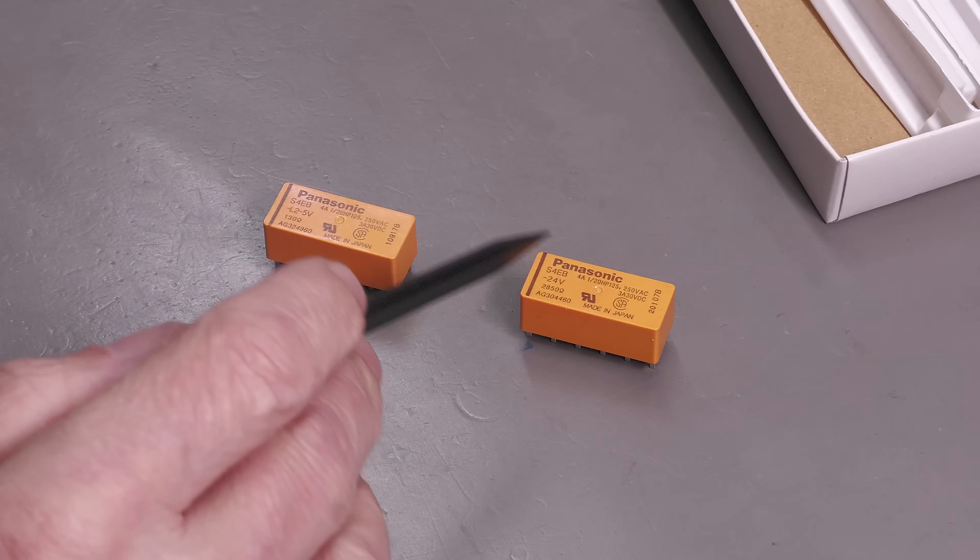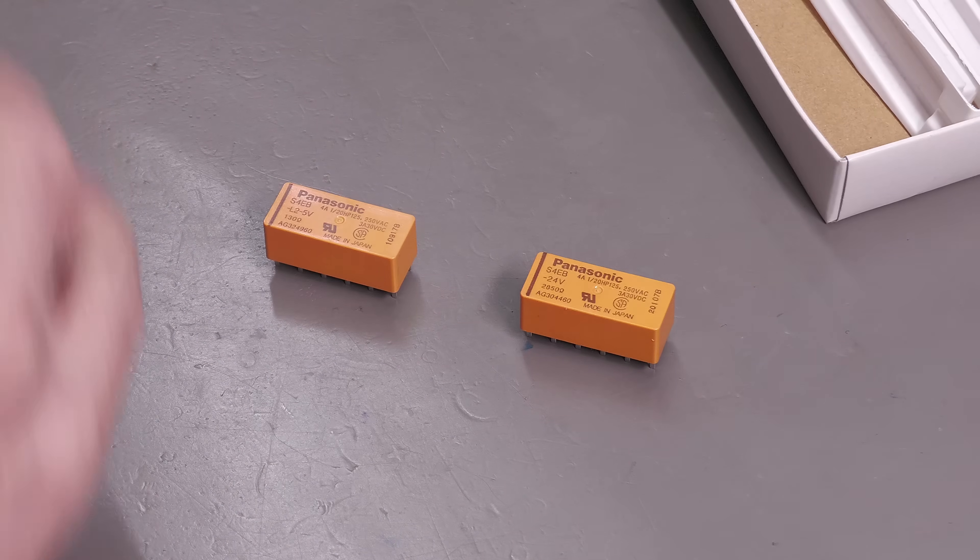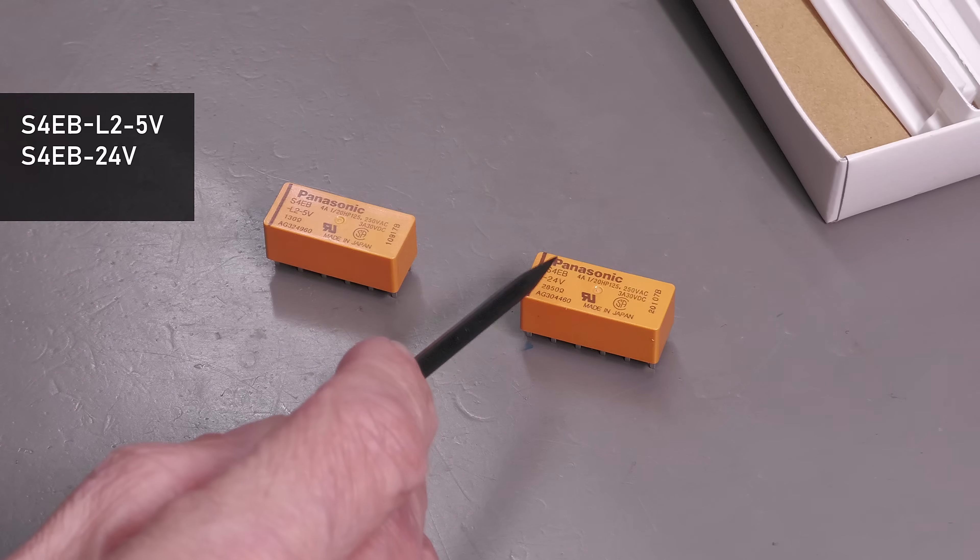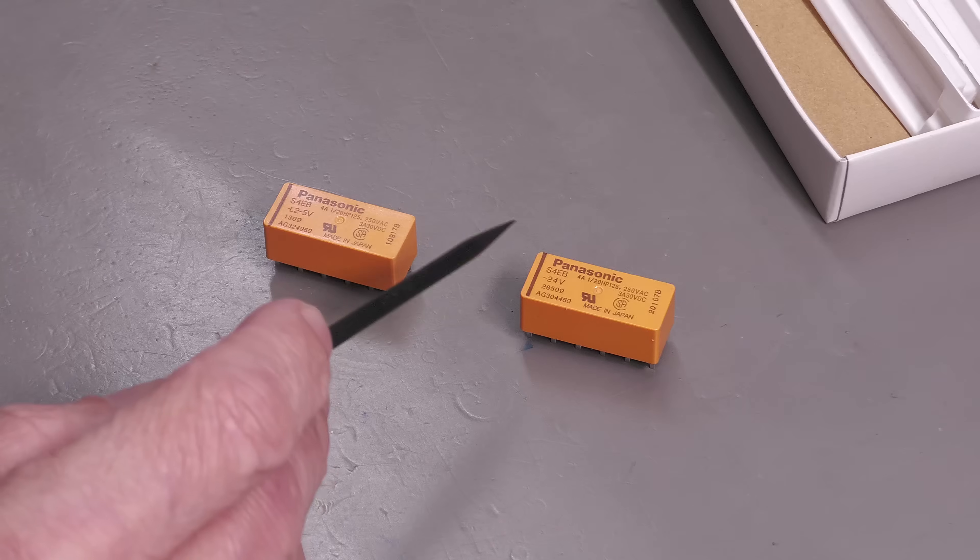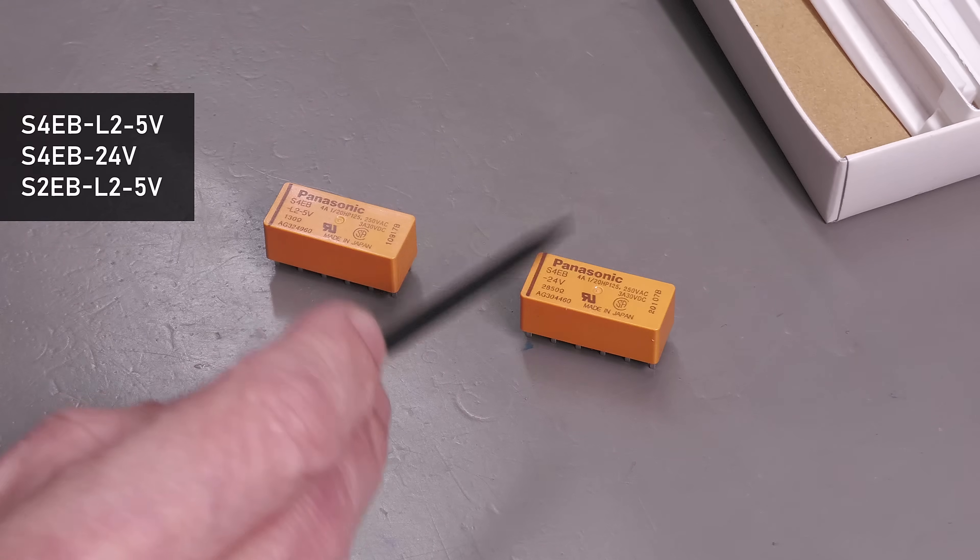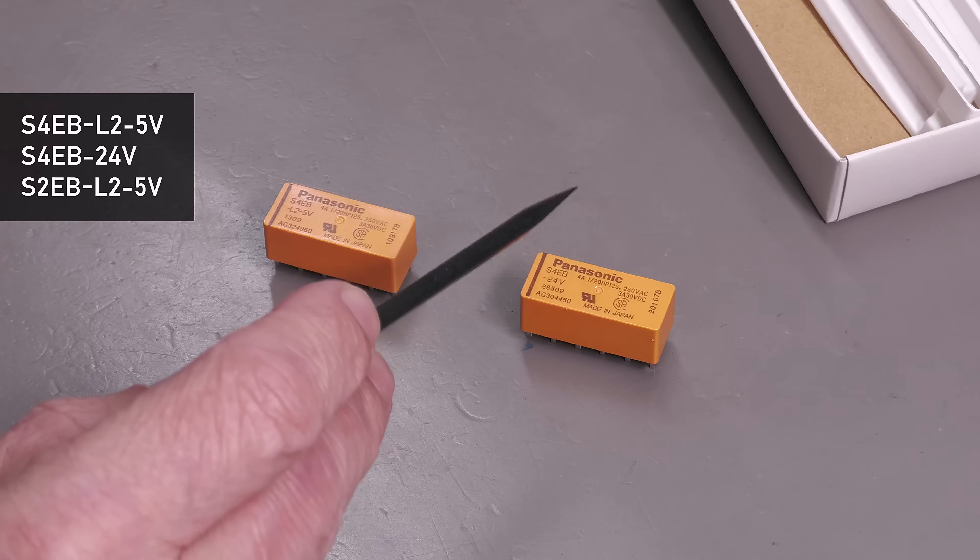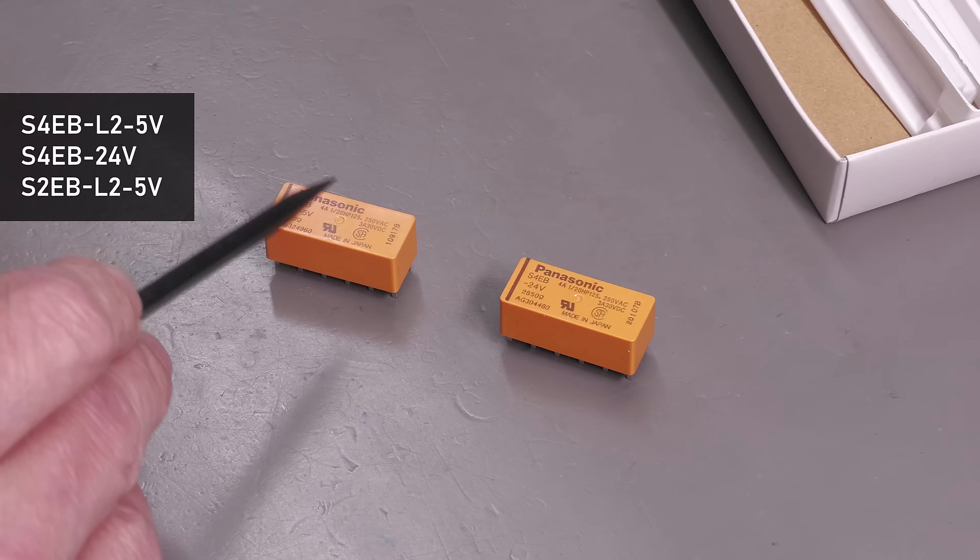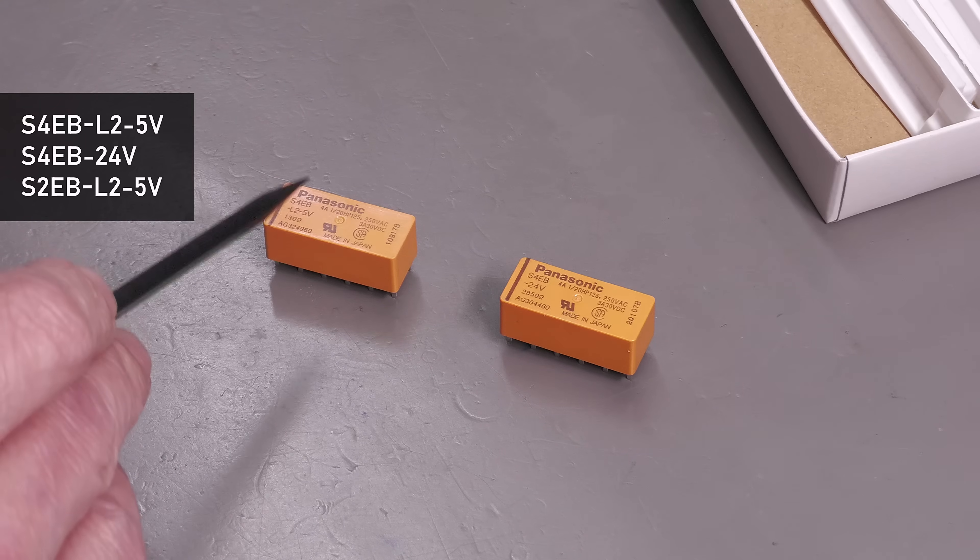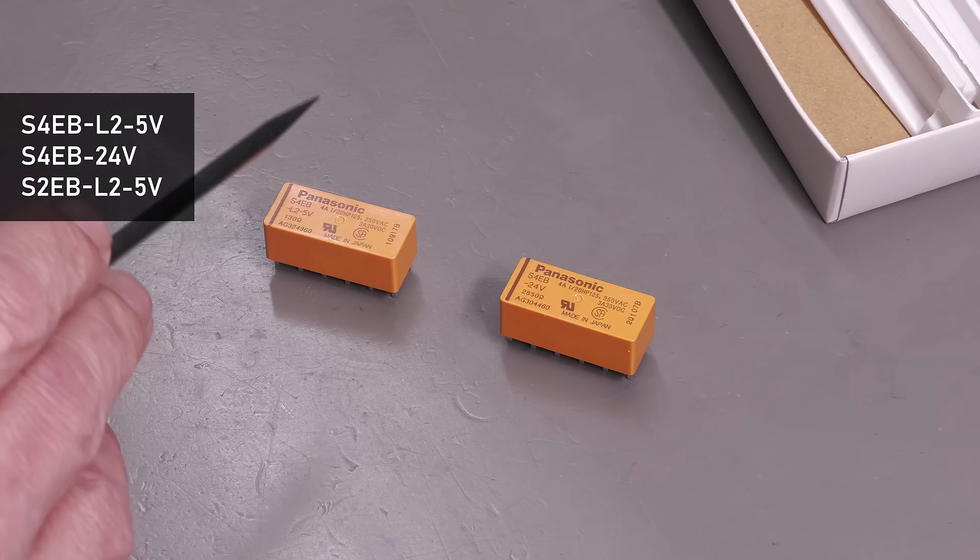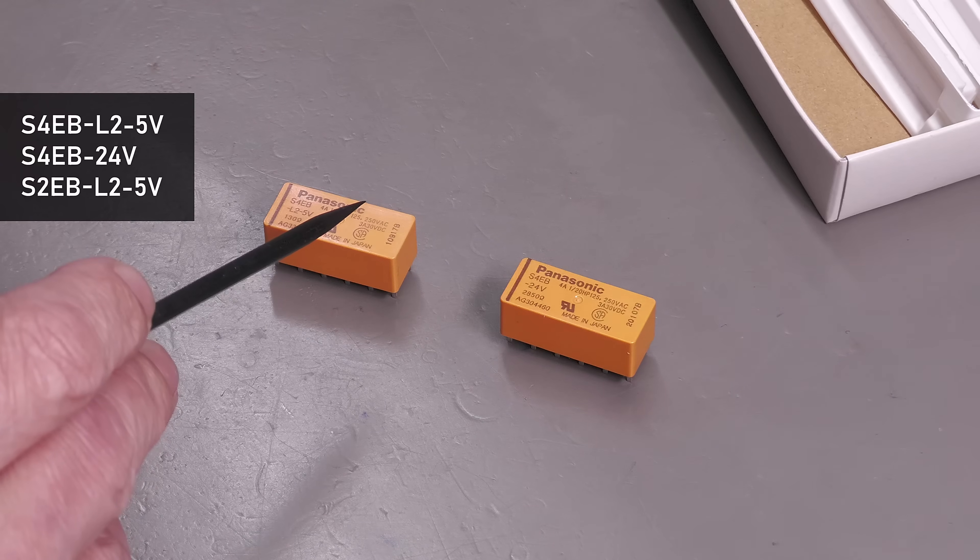Now out of the box I've only got two different types. There is actually a third type as per the original set but they're all fitted to the board. What we've got here is an S4EB-L2-5V, an S4-EB-24V and what's fitted to the unit is an S2EB-L2-5V. Looking up the datasheet for those relays, I think the S4-EB-24V is perfectly suitable, that's a four Form A with four normally open contacts, single coiled 24-volt relay. So the 24-volt one is good to go. However, the other two, the S4 and S2-EB-L25Vs, L2 refers to a two coil latching relay which we don't have fitted to the 1281. So I think the relays were ordered, two of them are not suitable and only the 24-volt one is. Wow. So no much wonder the unit can't change ranges.